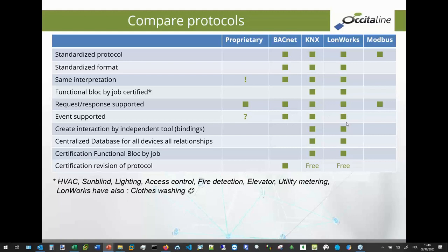It's completely different. Is request response supported by the protocol? Yes, for every device. In Modbus, for example, because it works in master-slave, the master sends a request to the slave and the slave responds. I am pretty sure that the proprietary has exactly the same, and request response is supported in BACnet, in LON, and in KNX too. For event support, I have no idea for the proprietary. For Modbus, it's void. You can't create an event with propagation when you modify a register, but in BACnet, in KNX, in LON, it exists. There is a small difference in BACnet compared with KNX and LON, and we will explain that just after.